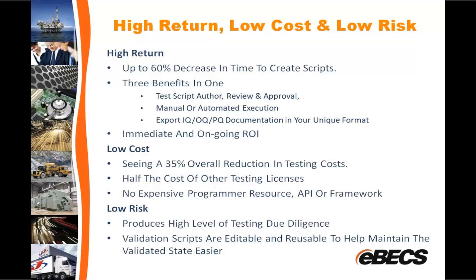It's important to understand, however, that it doesn't change the software. So if the system is simply capturing screenshots and that's all the system is doing, the system wouldn't need to be validated. But if it's going beyond that, allowing you to execute the scripts and to sign scripts, it does require validation. All right, great. Thanks very much, Val. Thanks, Mike.